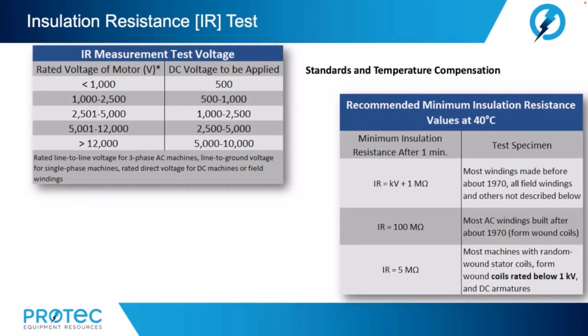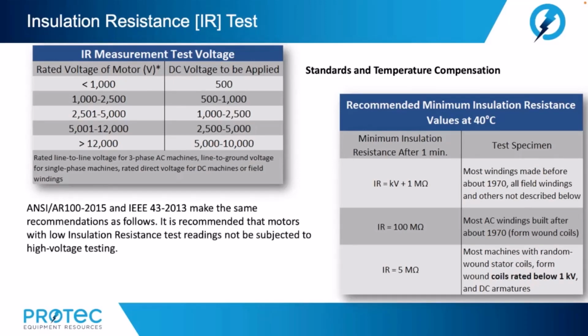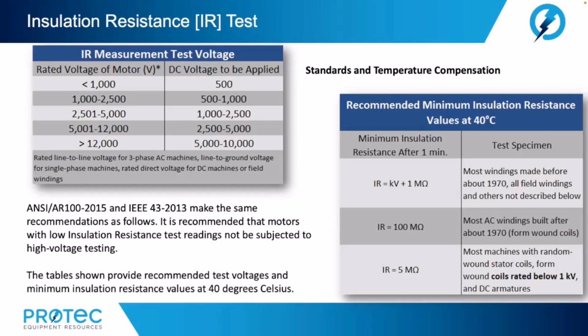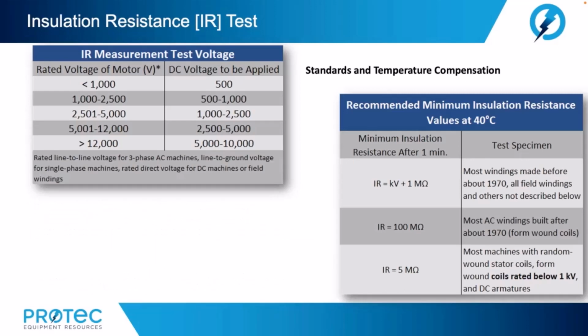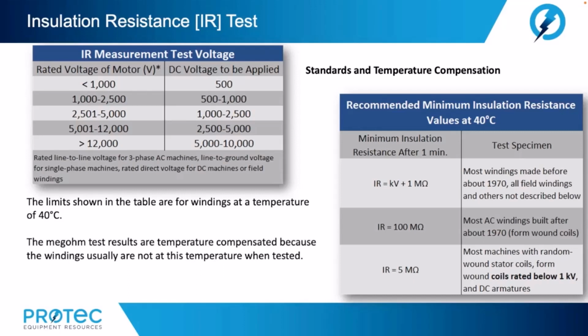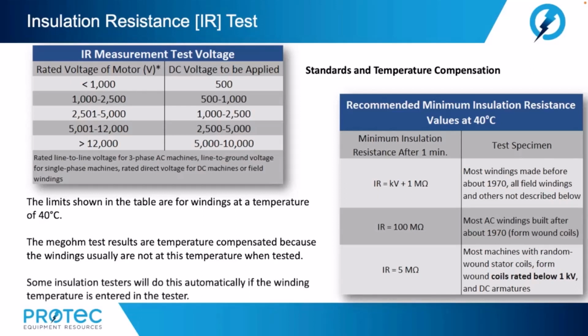Next, let's take a look at standards and temperature compensation. ANSI AR100-2015 and IEEE 43-2013 make the same recommendations as follows. It is recommended that motors with low insulation resistance test readings not be subjected to high voltage testing. The tables shown provide recommended test voltages and minimum insulation resistance values at the standard temperature of 40 degrees Celsius. The limits shown in the table are for windings at a temperature of 40 degrees C. The megohm test results are temperature compensated because the windings usually are not at this temperature when tested. Some insulation testers will do this automatically if the winding temperature is entered into the tester.